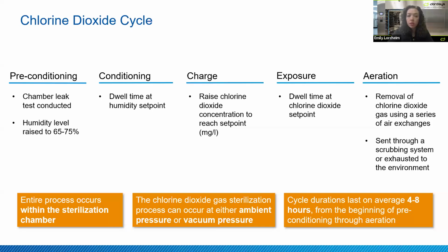So this is just a little basic on the chlorine dioxide gas cycle. Again, almost identical to how ethylene oxide looks. So we're going to have preconditioning. We're going to first do a leak test and then raise the humidity level, generally 65 to 75% relative humidity. We're going to let that humidity sit in the chamber with the product for a specified period of time, typically 60 to 90 minutes. We're going to introduce chlorine dioxide gas into the chamber, leave it sit there for a specified time period until we reach our dosage.